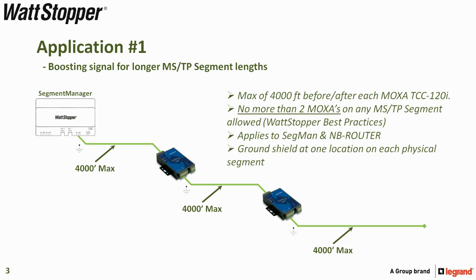You can have no more than two Moxas on any MSTP segment. These are Wattstopper best practices. This applies to the SegMan and NB-ROUTER connections, and as shown, ground the shield at one location on each physical segment.